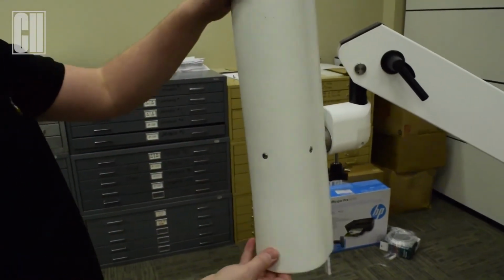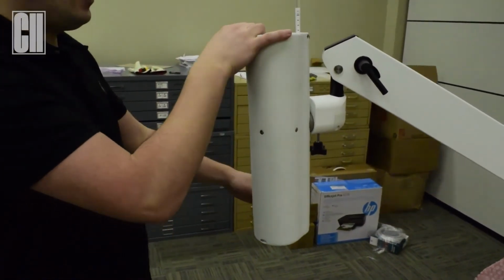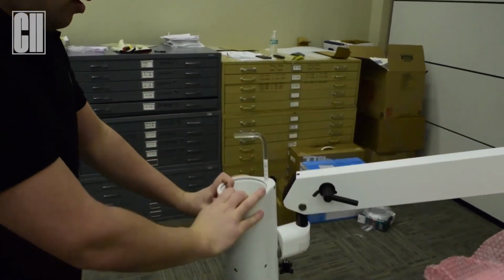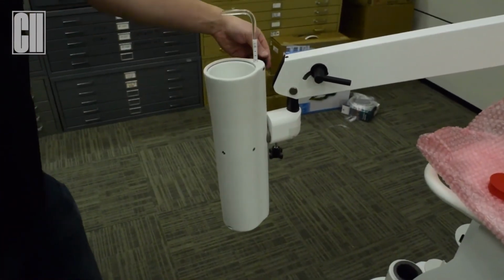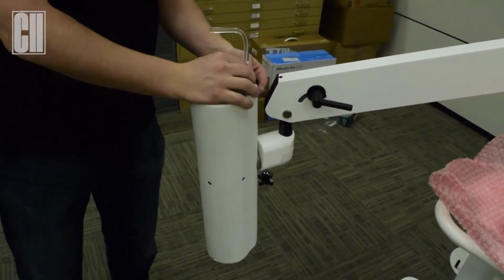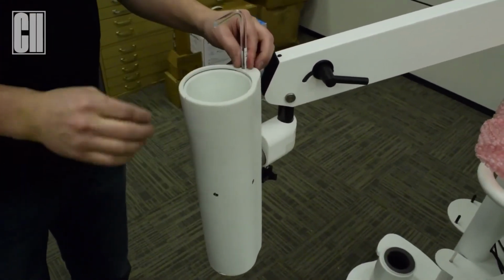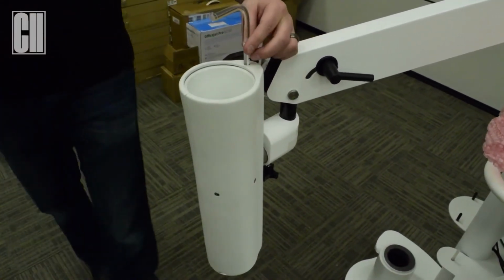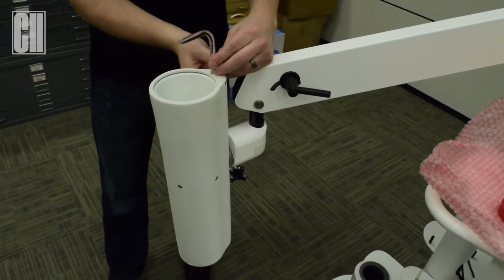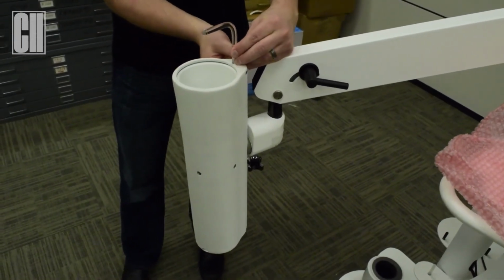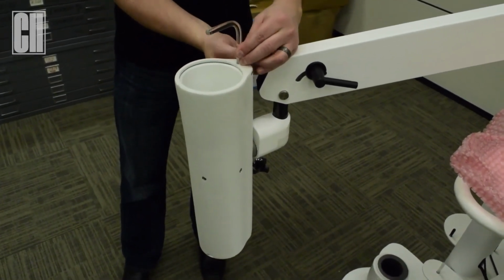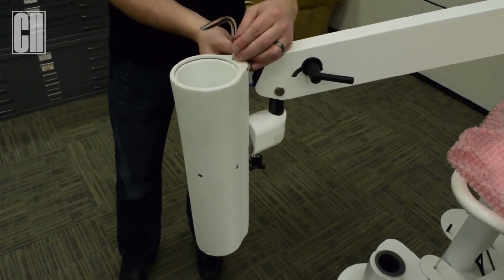Once that's tightened, you can then turn the collimator back and it's ready to go. This device here on the collimator is your screw tightener for the pointer rod. Typically it's set at 25 centimeters. Depending on the facility it might be a different distance, but once you have your distance, you can use a screw to tighten it, and that would be your exact distance for your uptakes.